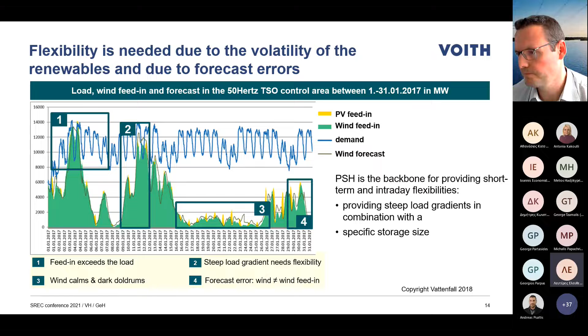So let's have a closer look at pump storage systems. At a glance, such systems can operate and produce from standstill to full power in around 90 seconds; smaller units can do it even faster. Basically, it's not really driven by the unit itself, but more by the waterway and water reservoir settings.